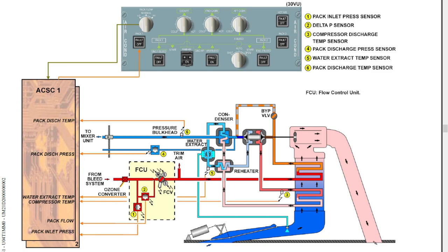So if the corrosion happens, this can get seized, and it will lead to heavy maintenance costs. So to get rid of that moisture which would be introduced to the turbine side, you reheat it, get rid of the moisture if present, and you introduce air to the turbine. At the turbine, normal physics, air gets expanded, and that energy is absorbed by turning the turbine.